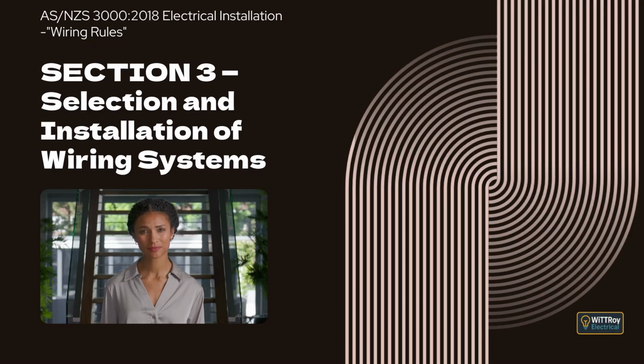Clause 3.10.3.6 Terminations. This clause explains that wiring enclosures must terminate at electrical equipment in a way that fully protects the enclosed cables as they enter the equipment. Flexible conduit must be securely anchored at each end to fixed conduit, structures, or equipment.